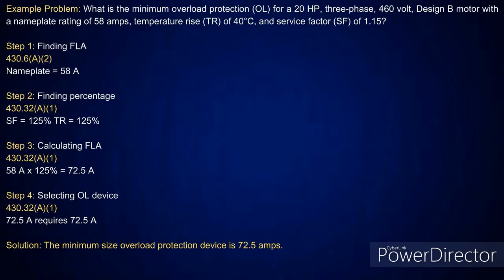Now, as you look at 430.32(A)(1) for your separate overload device, it's going to tell you motors with a marked service factor of 1.15 or greater is 125%. Then motors with a marked temperature rise of 40 degrees C or less, we're at 40 degrees C or less, 125%. I have to meet both of those. If I didn't, then I would do it at 115%.